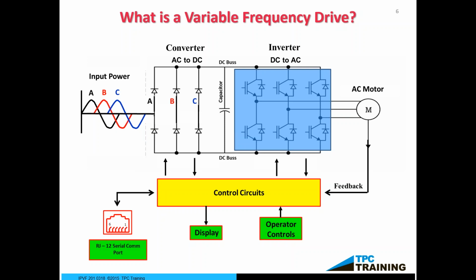So from a troubleshooting aspect, we've got incoming power, and then we have DC, and that DC is converted over to a pulse width modulated signal. I guess what I'm saying is the input is traditional, the output somewhat of a square wave. And I might add also, your multimeters may or may not read that output signal. So it's really important as we look down at the display, the ability to go through the display and see what you're looking at. Not all multimeters will read that pulse width modulated signal. And during the course, you'll see we'll talk about RMS, root mean square, and some other calculations that we need to go over. But let's just one more time take a look at this particular circuit.